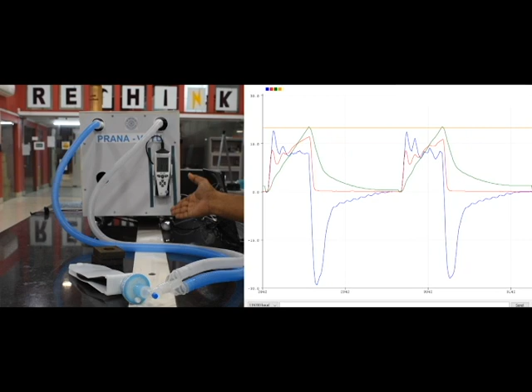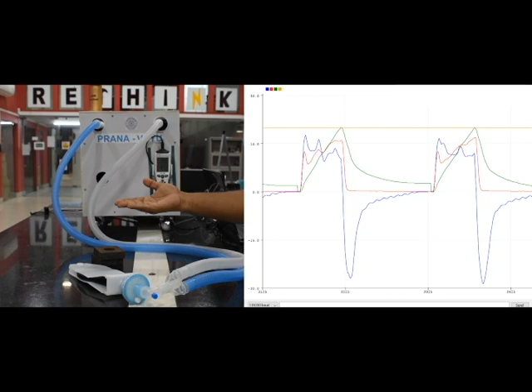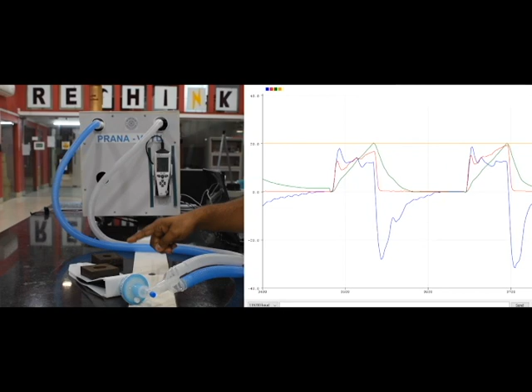Now the simulation is running for CMV VC mode. That means the target is to reach the fixed tidal volume, and here you can see that first we are putting this weight of 650 grams. Still the ventilator is supporting this constant tidal volume, and it is reaching up to 400 ml tidal volume. And then if we put another weight, which is equivalent to 1.3 kg, you will still find the ventilator is able to deliver 400 ml of tidal volume.